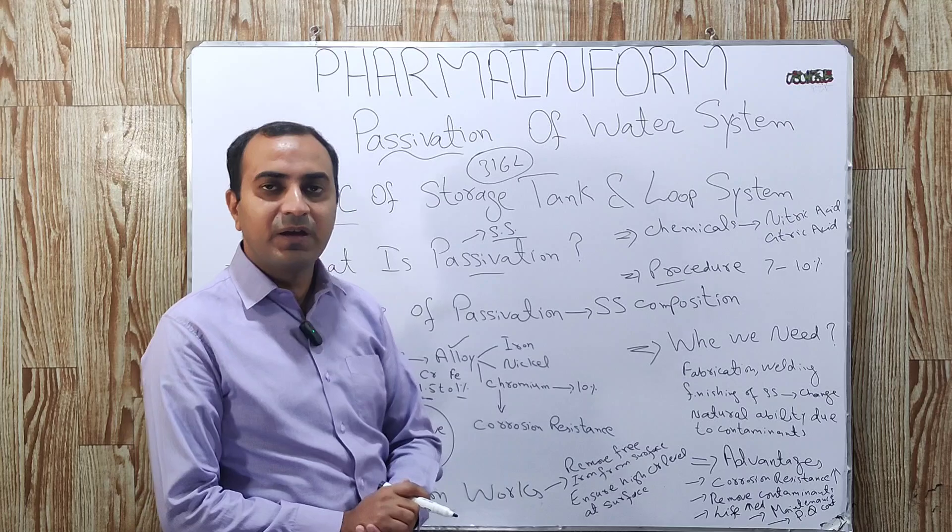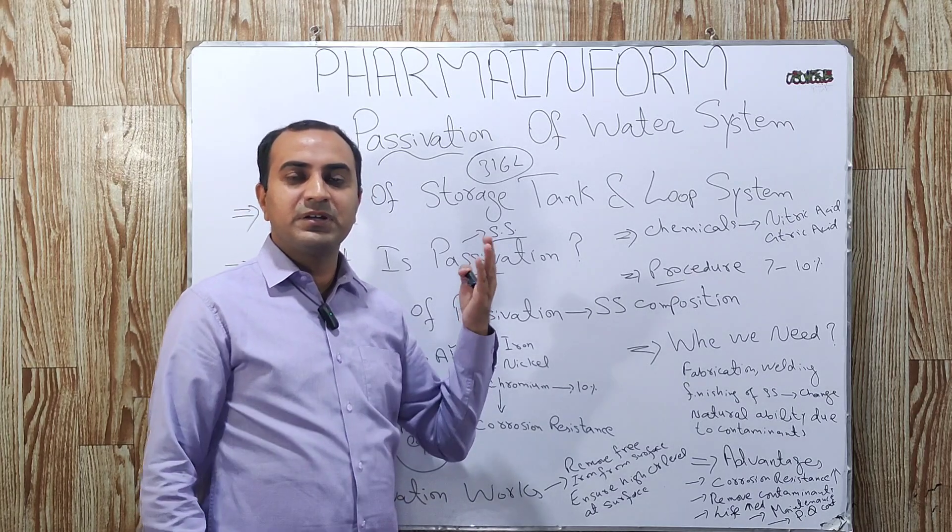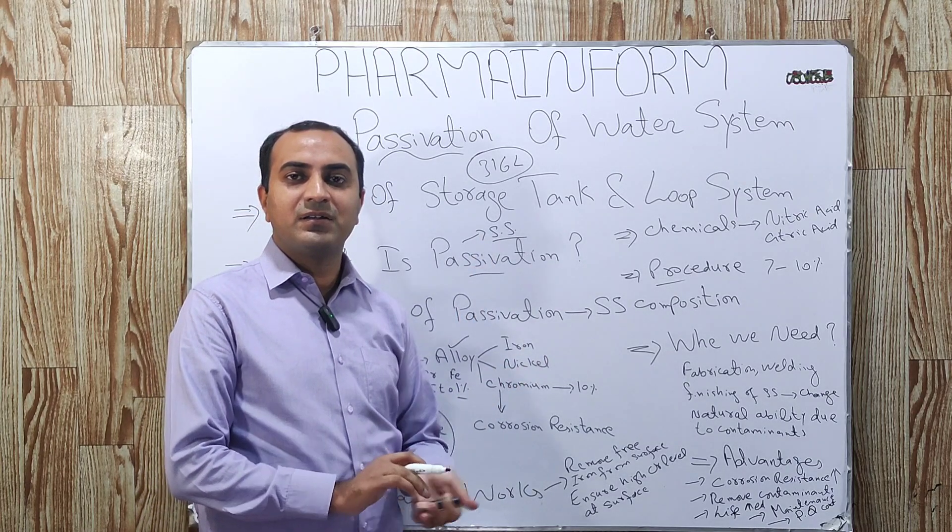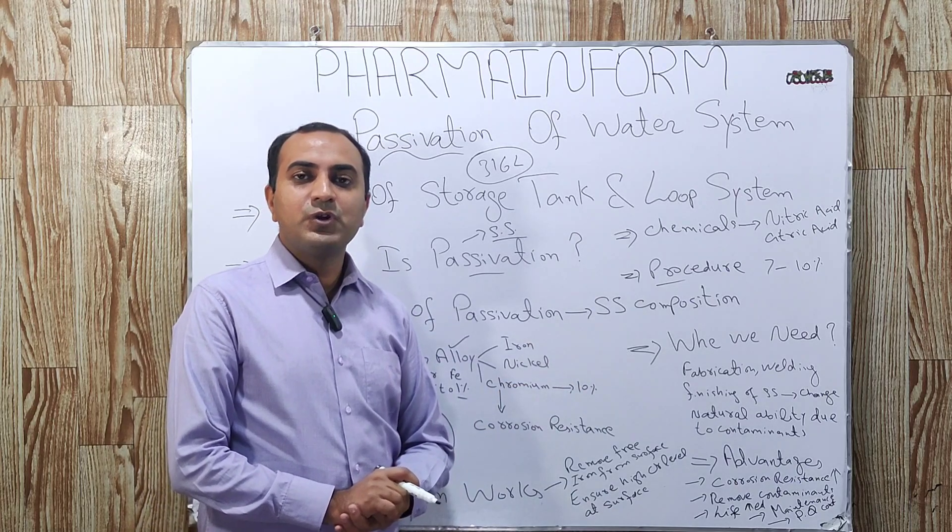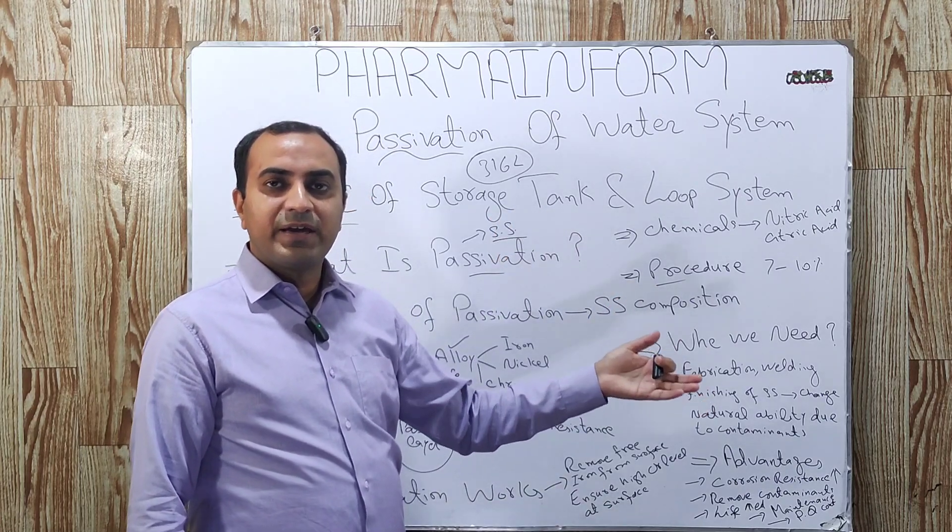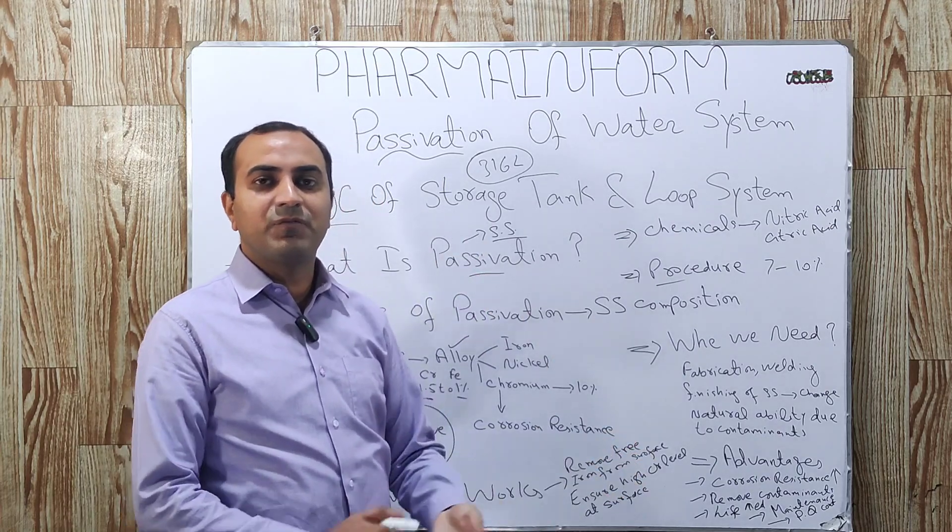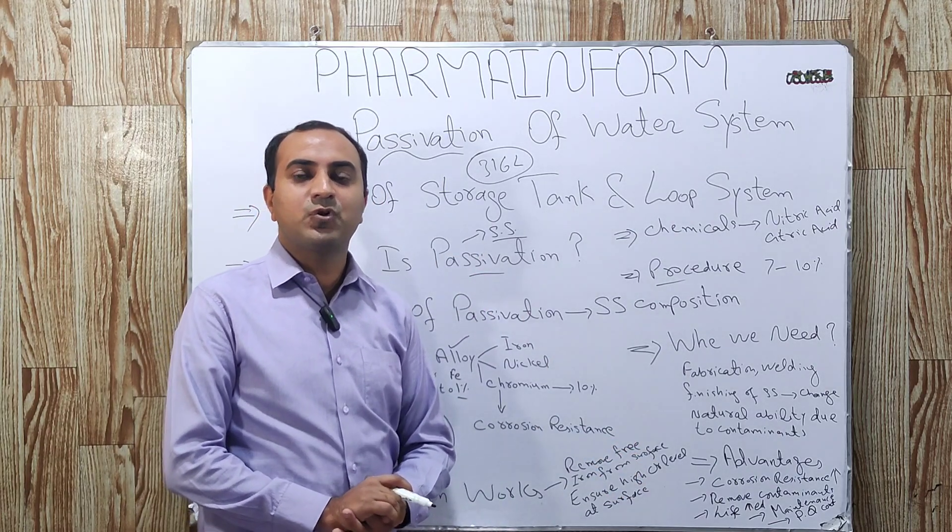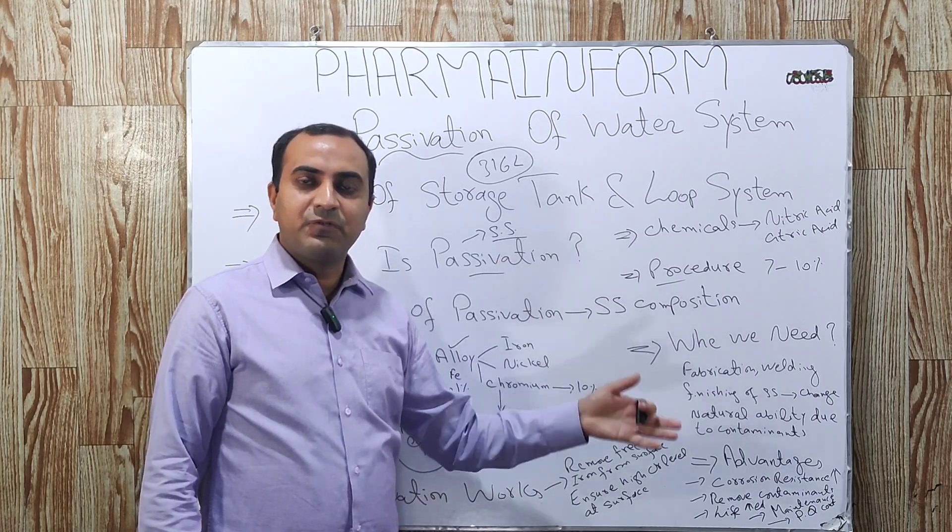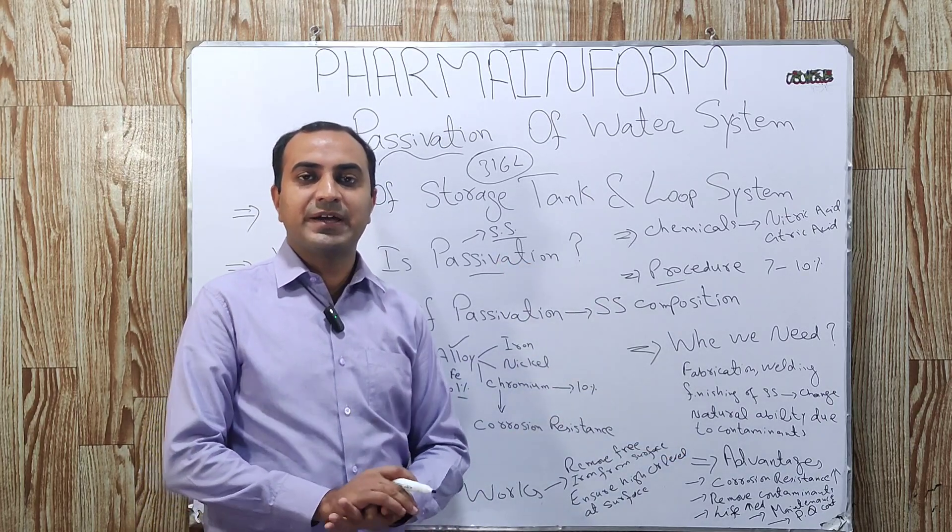After 2 hours, we open each user end and discard the nitric acid solution. Now, we fill the storage tank with the purified water, freshly prepared purified water and again circulate it for 1 hour. After 1 hour, we again check its pH and conductivity.